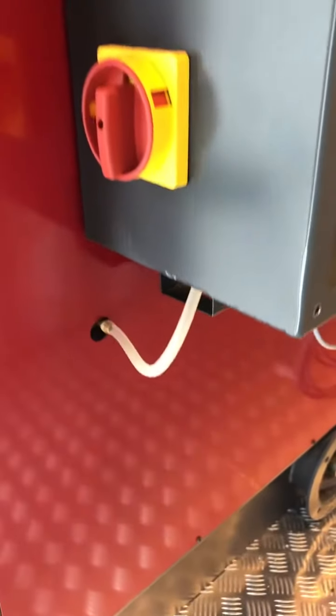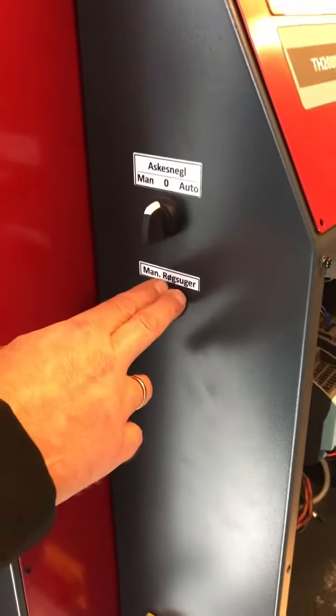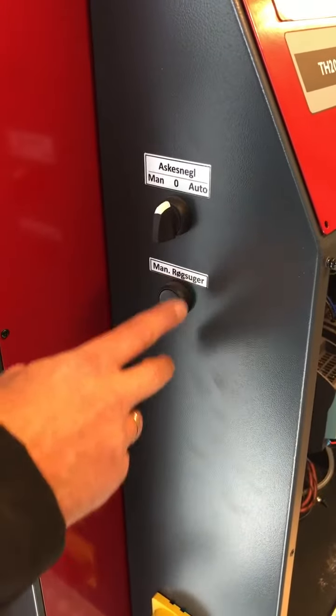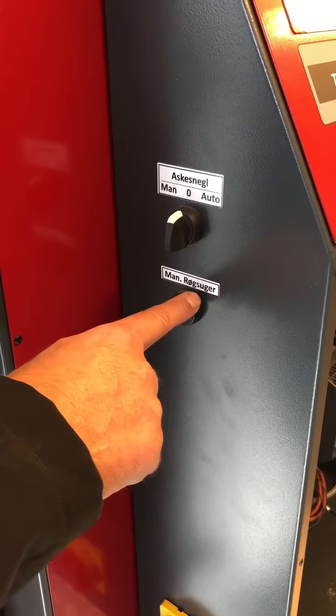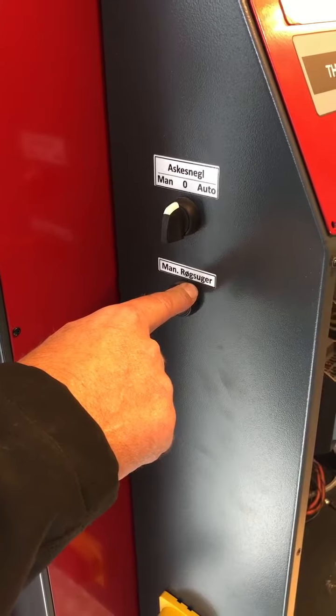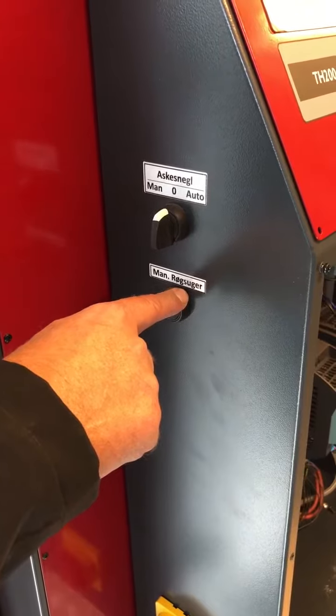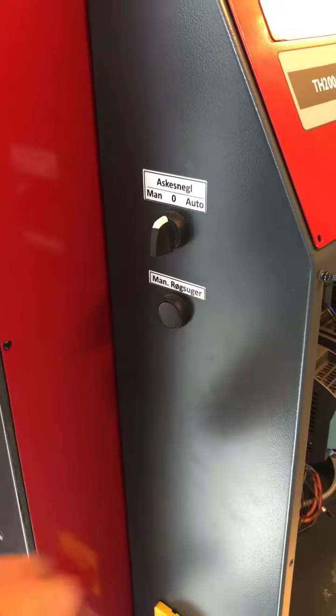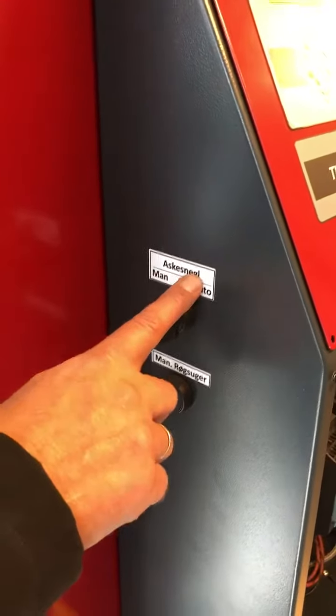Here we have the emergency stop. Here we have the main stop. This is where we feel the under pressure in the boiler. Here, if we open the door and want to clean the boiler, we can press this button and we go into manual fan exhaust. It'll rev up. So when you open the door, the fan will rev up and you take the smoke and the dust into the boiler instead. Here we've got the ash auger.